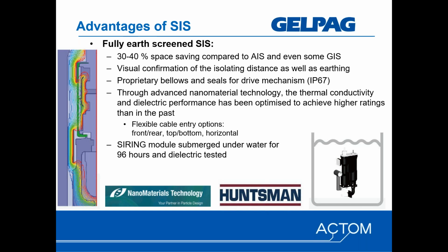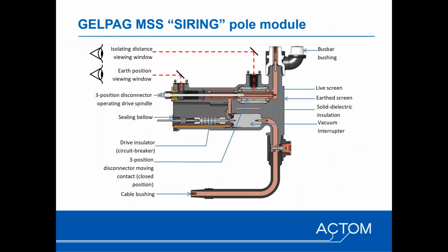What is also great about the modular, plug and play design of a solid dielectric solution is that you can very easily accommodate front or rear cable access, top or bottom, as well as direct rear entry, which we're doing currently for an e-house in a particular application we're working on. The solid dielectric module, which is called the SIRING module, has been tested underwater for 4 days, and then dielectric tested after that. Obviously, that would not include the operating mechanism. We're talking about the high voltage primary circuit. That's because all the dielectric stress is contained within the solid dielectric insulation, as Johan will talk about.